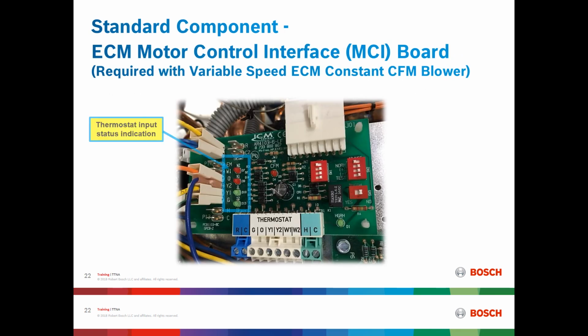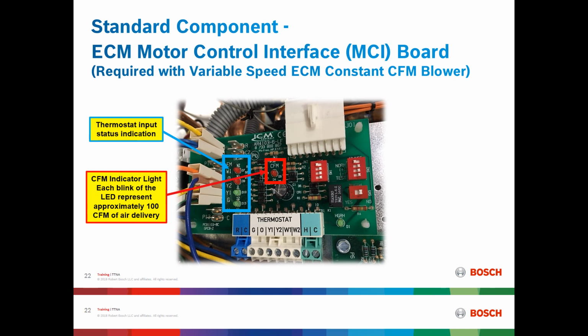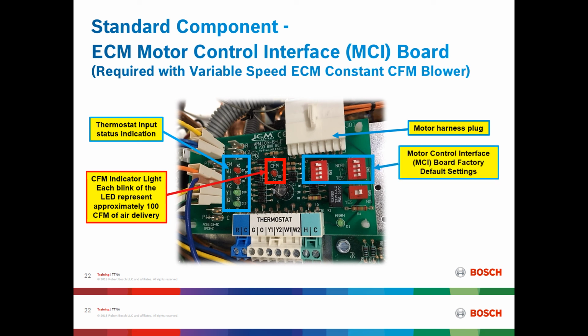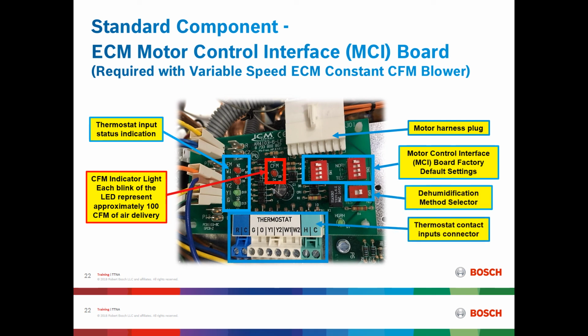That motor control interface board will be factory installed and provides thermostat input status indication. It also has a red light on the center of it that is a CFM indicator light. Each blink of that light, an LED light, represents approximately 100 CFM of air delivery while the machine is running. The top right is the motor harness plug connector. Below that are motor control interface board factory default settings. These will be used and set by the installer at the installation. Below that is the dehumidification method selector. At the bottom will be the thermostat contact inputs connector.